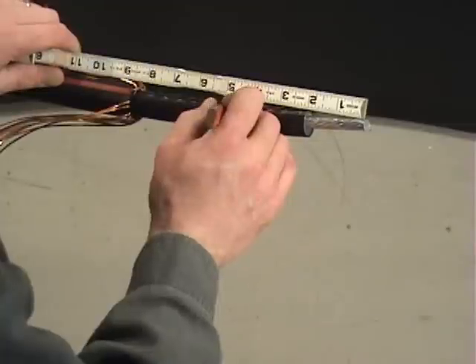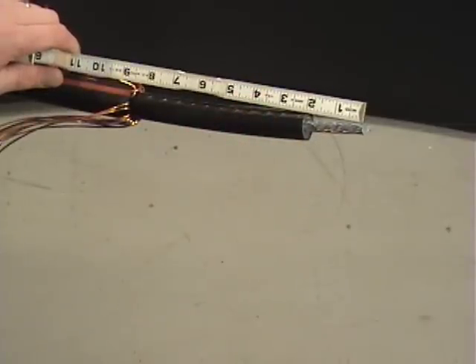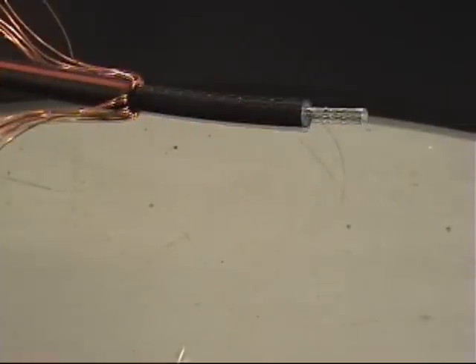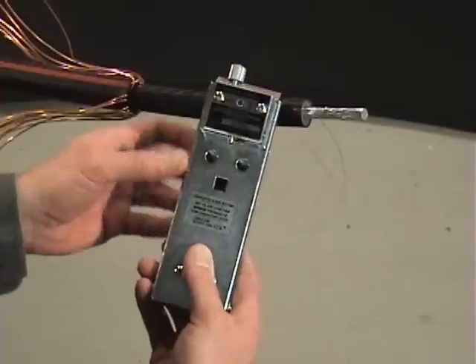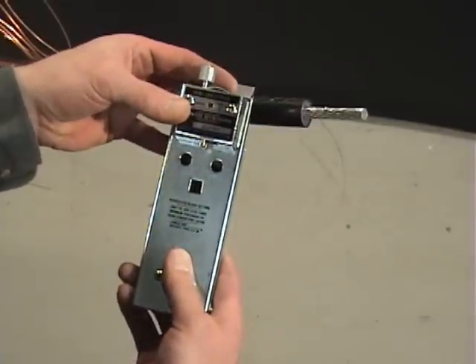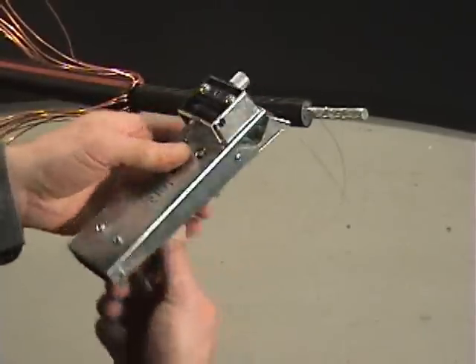Measure and mark the Semi-Con strip back according to the manufacturer's instructions. Set the Semi-Con scorer blade depth to cut through most of the Semi-Con layer without cutting completely through to the insulation.